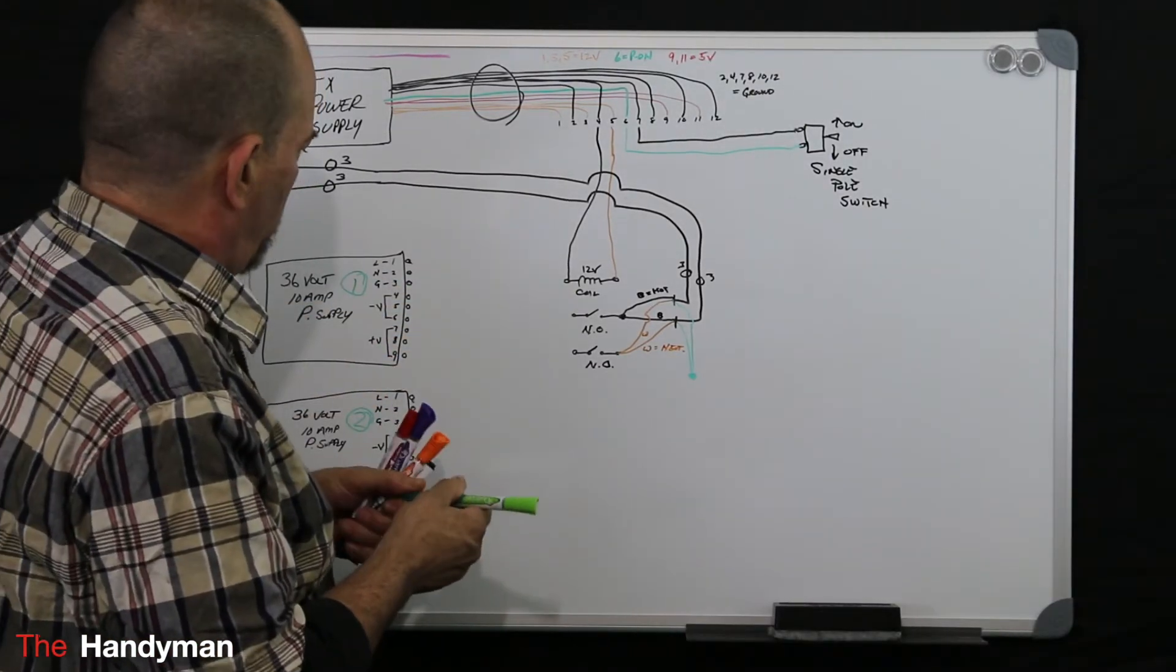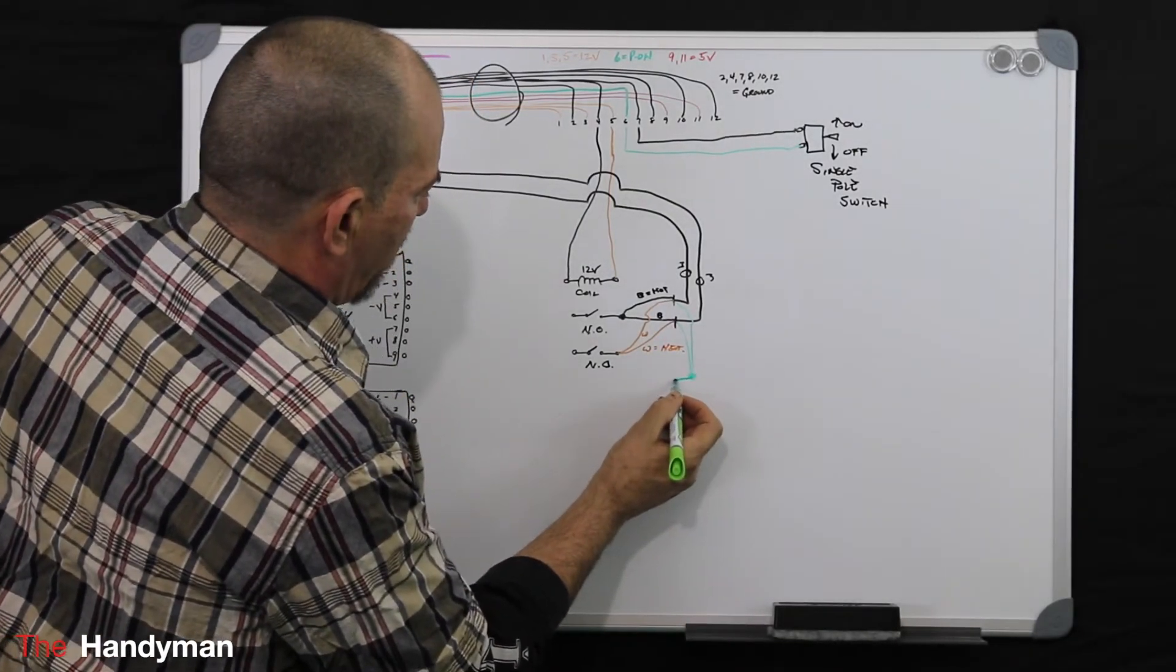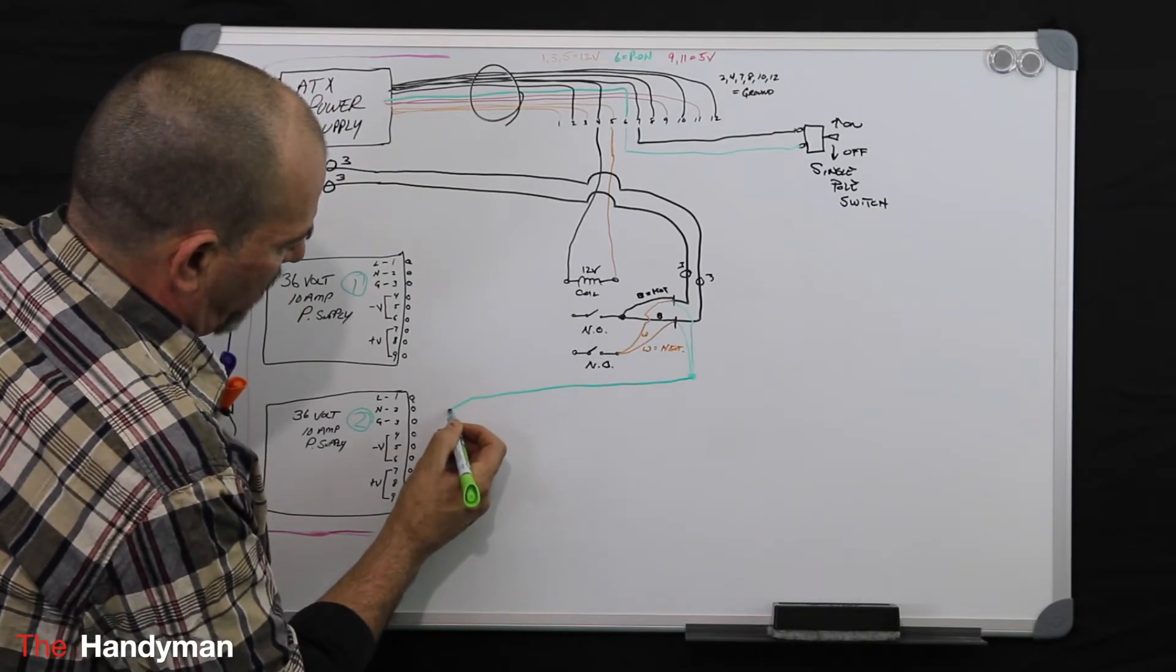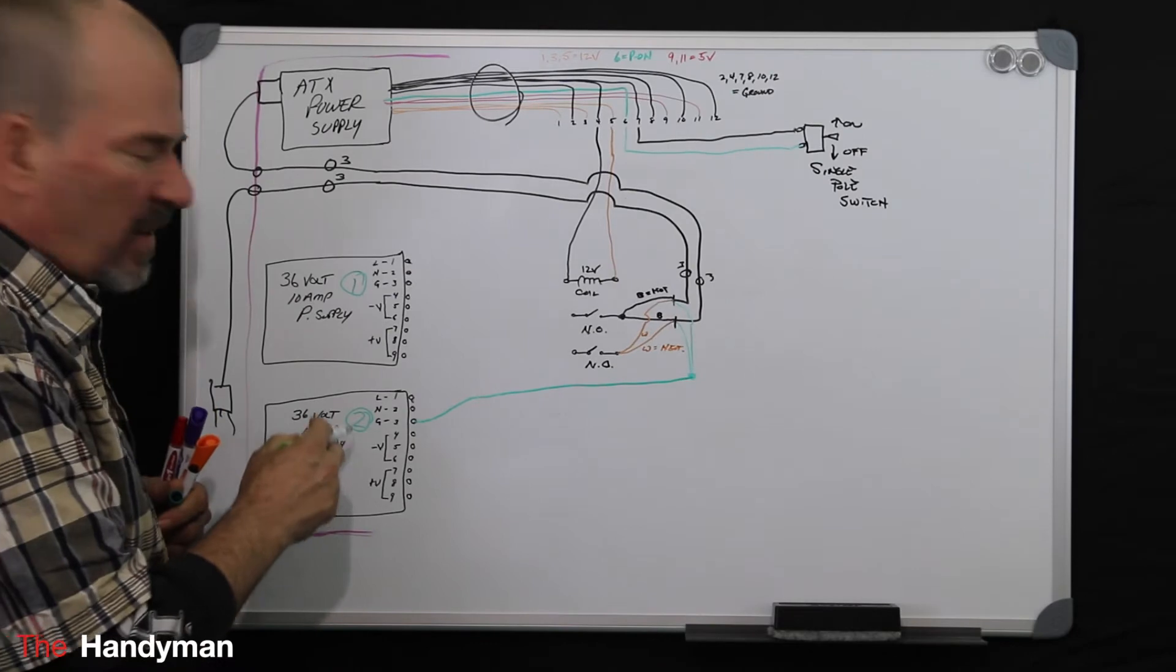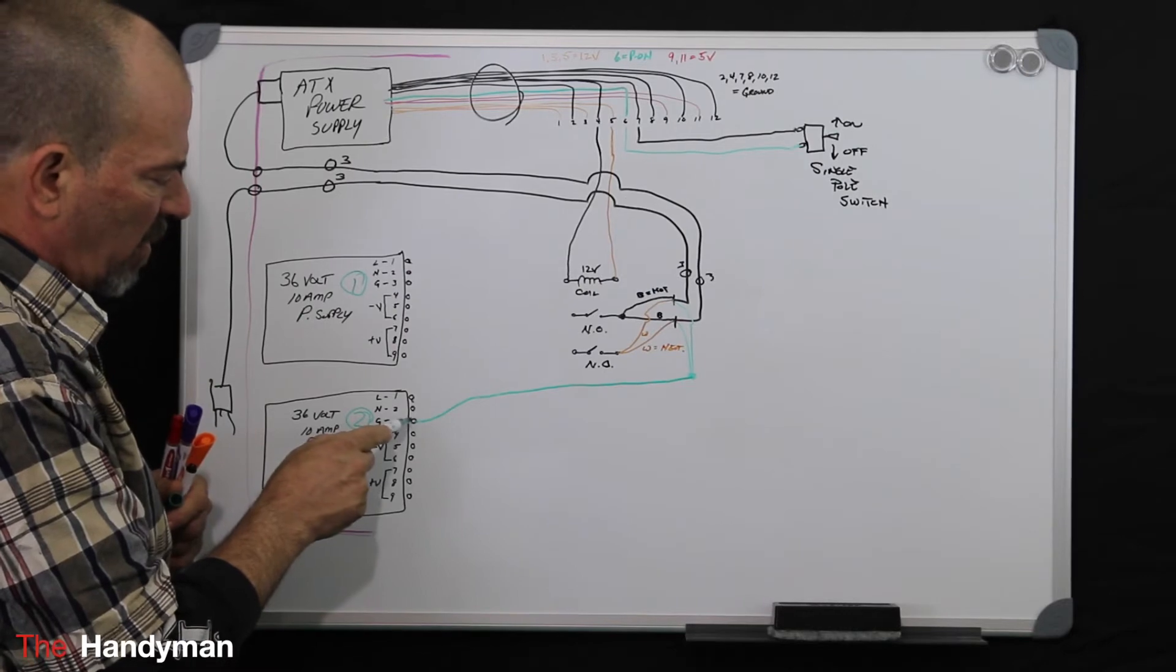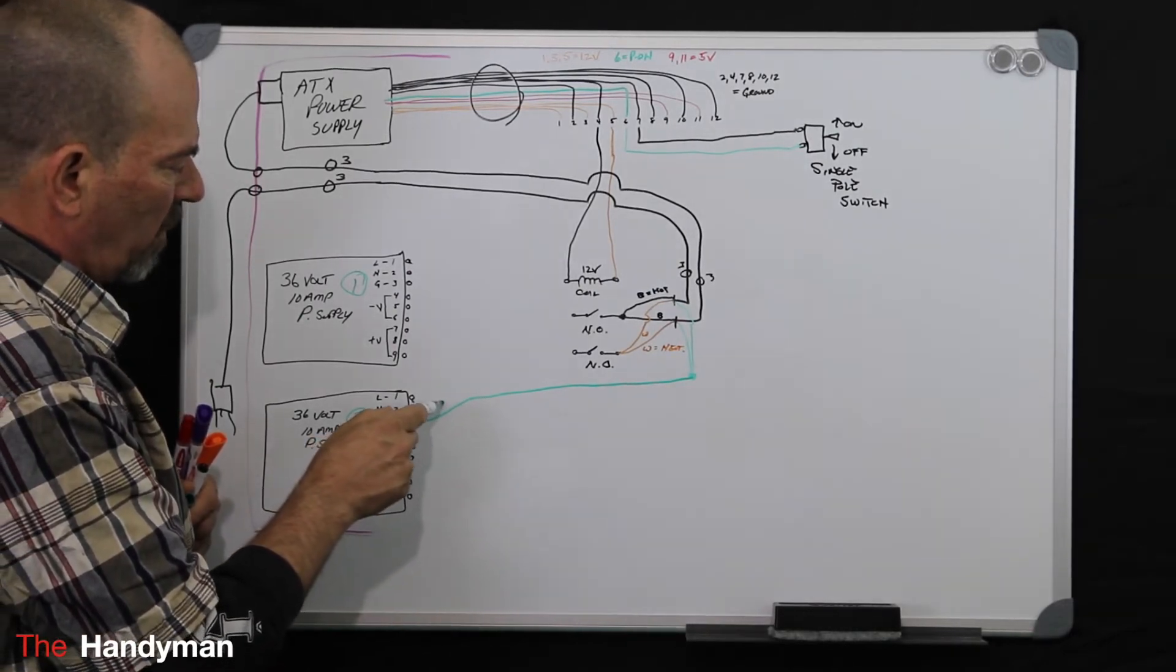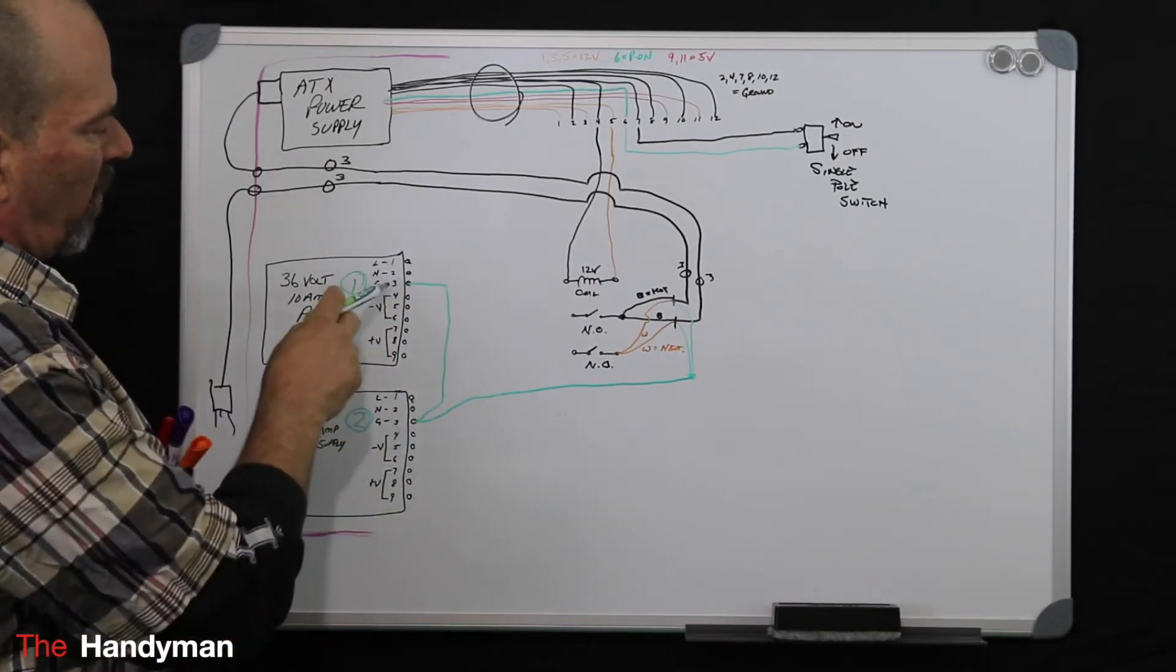So what we're going to do, you're going to take your ground, come over here, and on these power supplies that I bought, the ground is the third screw terminal. So you're going to land that ground under the third screw terminal, then make a jumper, come up, and go to the other power supply to the ground screw.